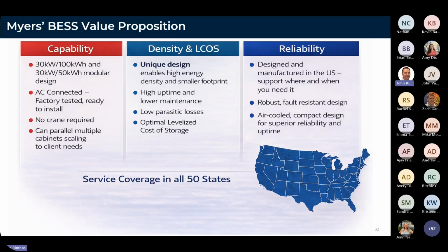We had a real use case up in Portland, Oregon, where an Eaton solution was being looked at, requiring a 125 kilowatt, 250 kilowatt hour BESS system. Theirs is a containerized solution, so they had to use 2 container units to get the kilowatt hours they needed, where we only needed 1 of our cabinets. That equated to about half the cost from a hardware perspective. And since our units have forklift pockets, no crane is required, which was an incredible advantage for the contractor and agent putting that project together.